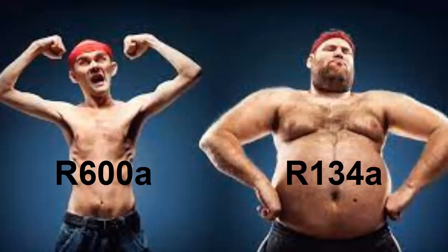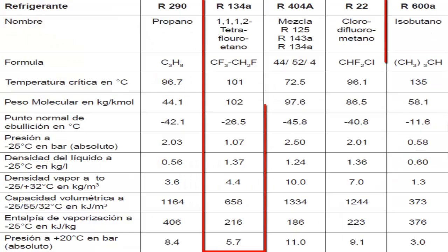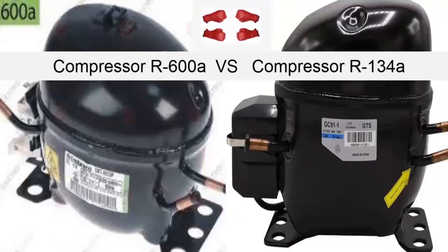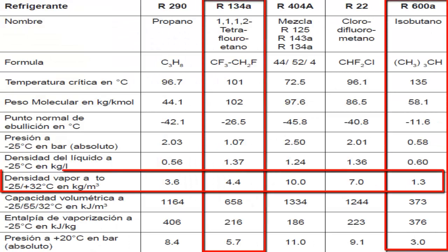In terms of refrigerant molecules, R134A in vapor state is heavier than R600A. This means that with a slight volume of gas passing through the compressor, several grams of R134A will be transported. Although R134A is less efficient in terms of cooling compared to R600A, the greater amount of grams passing through the R134A compressor ensures proper cooling of the product.